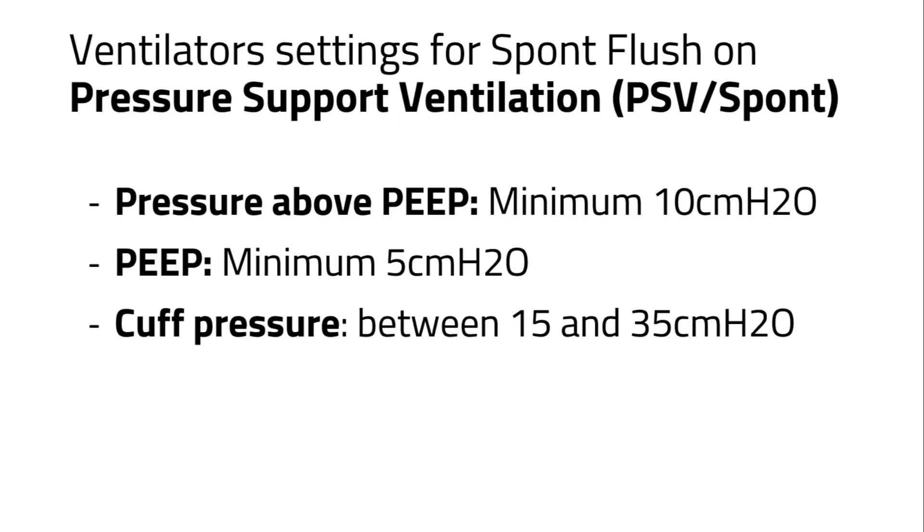Firstly, make sure the ventilator settings match the requirements of the Spont Flush device. The settings must be: pressure above PEEP, minimum 10 cm of water; PEEP, minimum 5 cm of water; cuff pressure, between 15 and 35 cm of water. If the ventilator settings are not met, the Spont Flush cannot be activated.